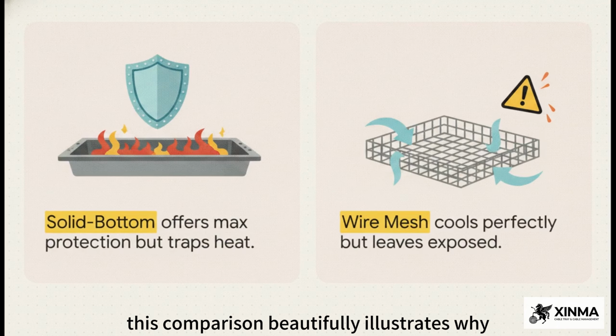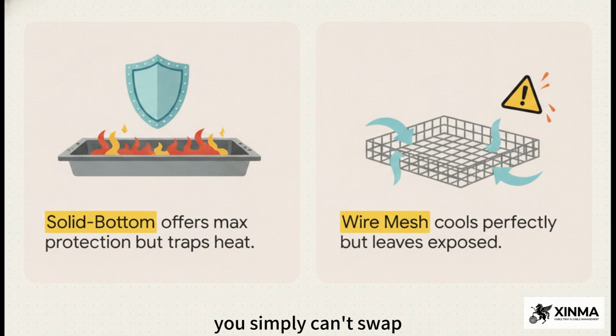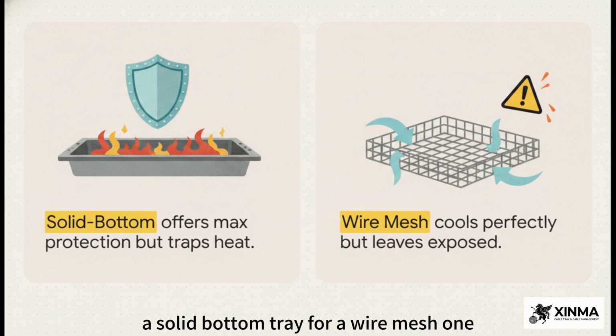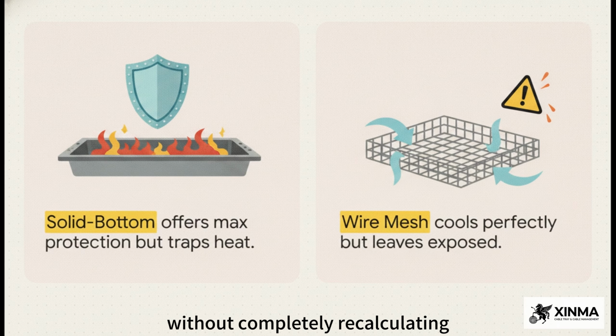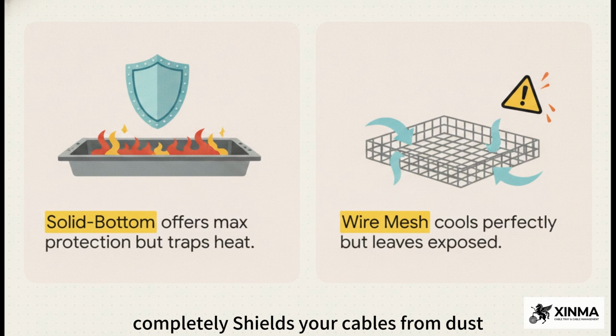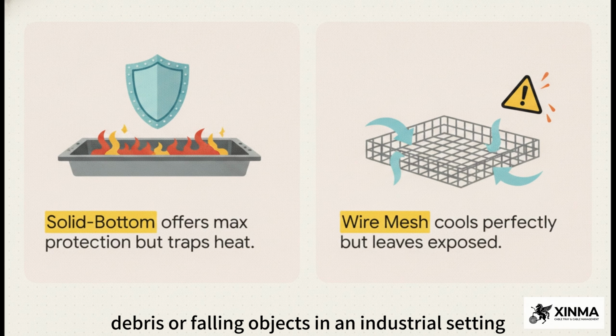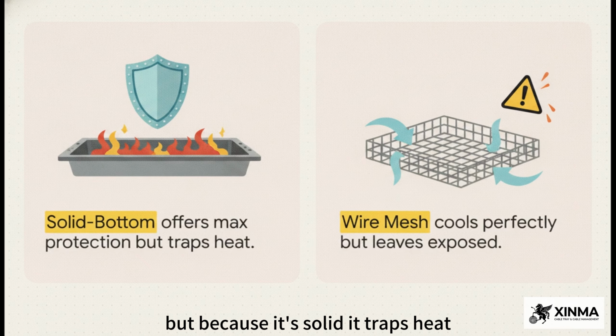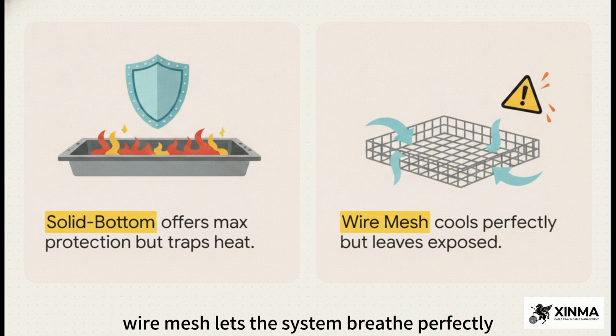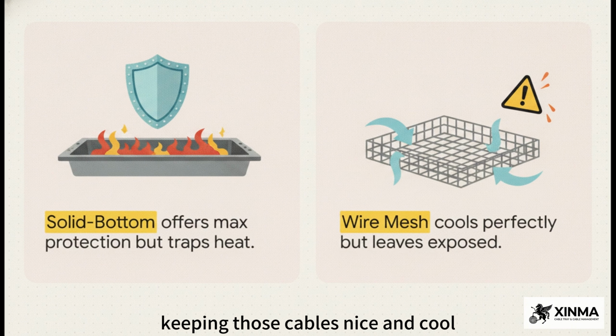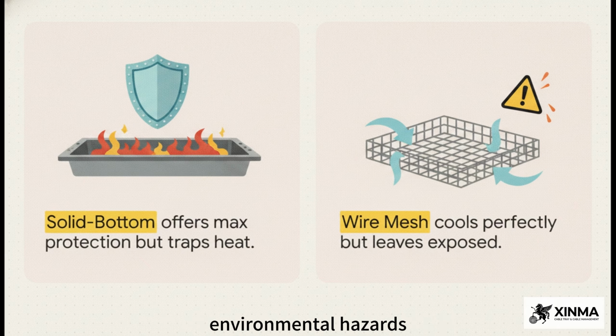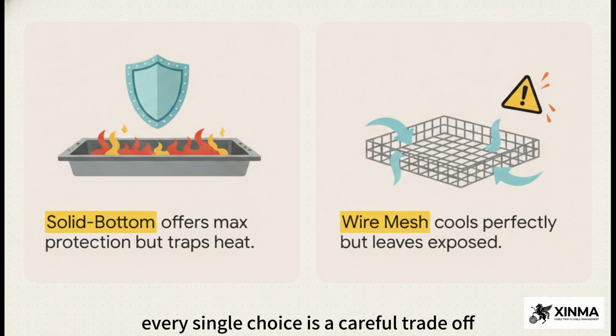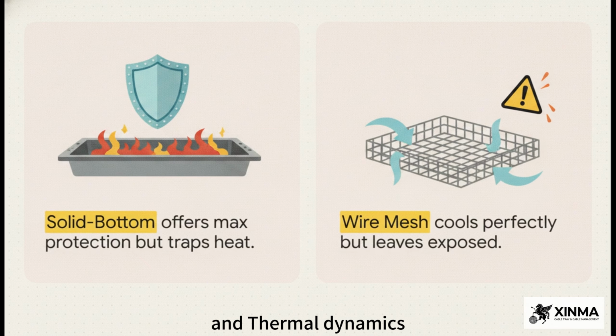This comparison beautifully illustrates why you simply can't swap a solid bottom tray for a wire mesh one without completely recalculating your load limits and thermal ventilation. A solid bottom tray completely shields your cables from dust, debris, or falling objects in an industrial setting. But because it's solid, it traps heat, which directly drops your ampacity rating. On the flip side, wire mesh lets the system breathe perfectly, keeping those cables nice and cool, but leaves them totally exposed to environmental hazards. Every single choice is a careful trade-off between physical protection and thermal dynamics.